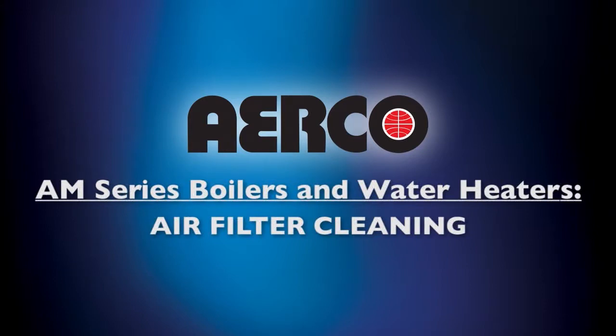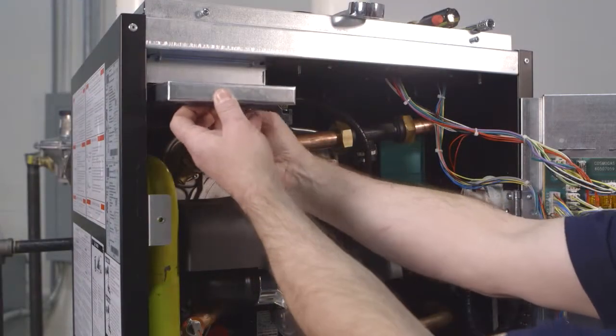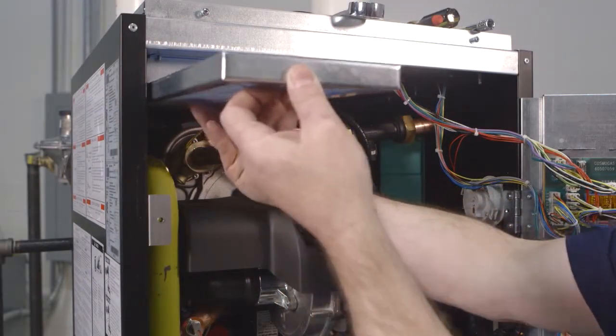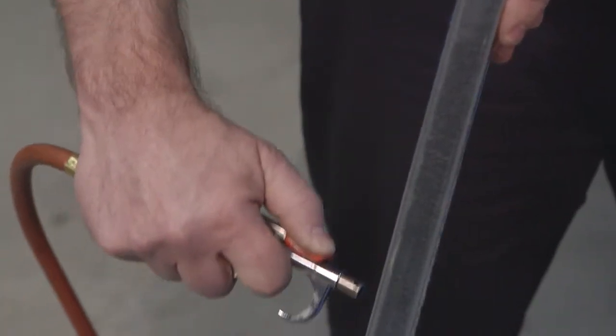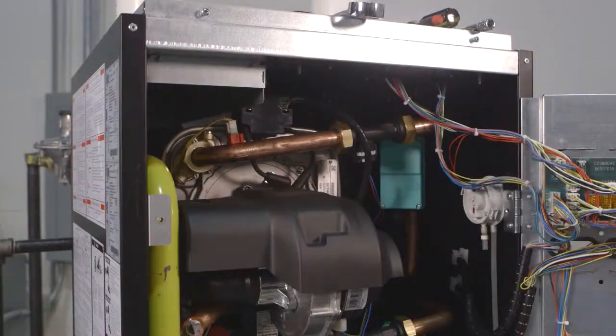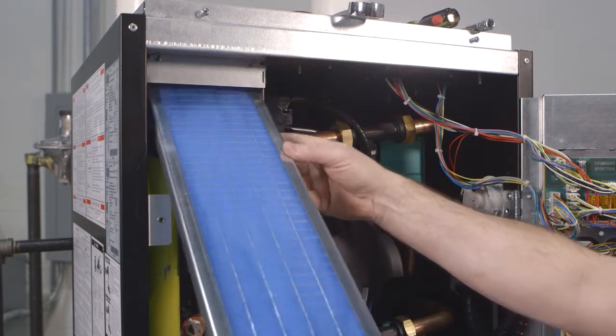For the unit to work properly, the air filter must be clean. A dirty air filter can cause a power input reduction of the unit, resulting in system malfunctions. Refer to your manual's instructions to gain access to the internal components. Now let's take a look at how to clean the air filter. Remove the air filter by pulling down and out. Clean the surface of the air filter using compressed air. Finally, reinstall the air filter.